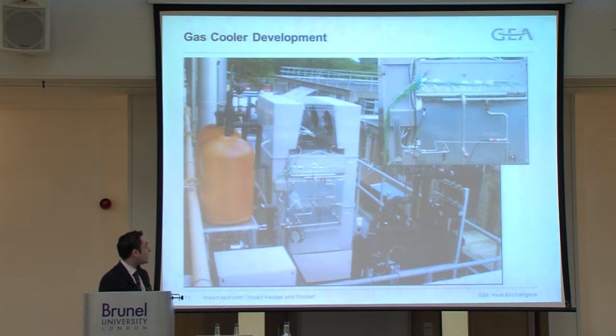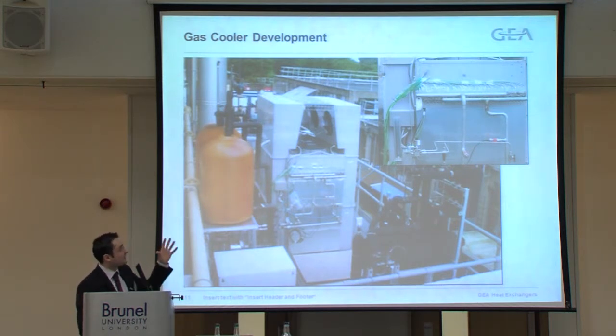So this is a graphic of what you'll be able to see later on. You can see we've got quite literally hundreds of temperature probes along every single circuit at regular intervals. Every couple of 100 millimeters, we're measuring the temperature to understand the temperature distribution across the gas cooler. This is actually quite an early photo here, so it just has 2 pressure transducers in there. Later on in the project, we actually installed another 4 pressure transducers, so on the inlet pipework, at the top of the headers, and after the header manifolds.